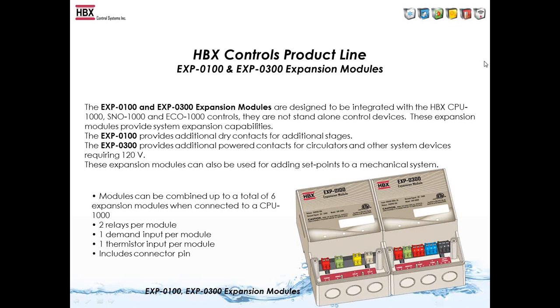The EXP300 is a wet contact expander. It has 2 wet contacts built onto it, and when we talk about wet contacts, that means we have 120 volt coming out of them already. So you would need to power up the EXP300 with 120 volt, and you can wire your pumps directly into the EXP. So this allows you to easily wire up pumps without doing a bunch of interconnections or junction boxes and other things like that.